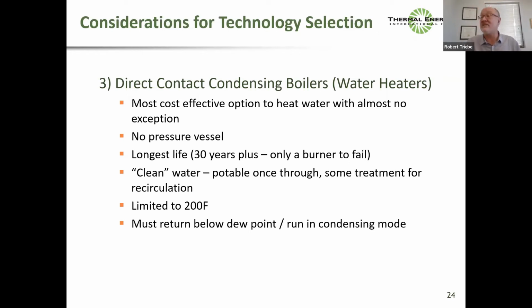It's got the longest life. The only thing to fail truly is a burner. And the systems do last 30 years. To the question that was asked, Mark, it's clean water. It's potable when it's once through, but there's some treatment for recirculation. And they're typically limited to about 200 F. So, however, it's not the most common hydronic boiler hot water heater that you're going to want to go over 200 F. But we must return below the dew point. We must run in condensing mode.